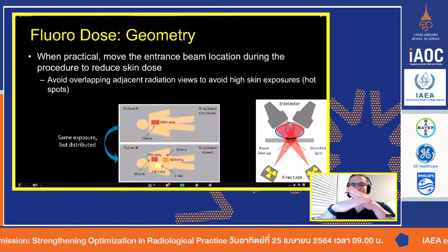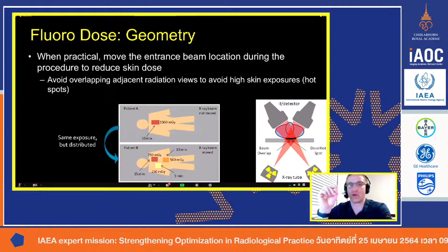Some of the newer interventional systems, because they know the table location and they know the tube position, will warn you if there is a hot spot, if there's an overlap. So as you're going along, you're seeing the dose map on the screen in real time. And if you angle, it'll immediately warn you that there is an overlap. You might be aware of it, or you may elect to move forward even though you know that there's an overlap. But at least some of the newest systems are becoming smarter and they're warning you.